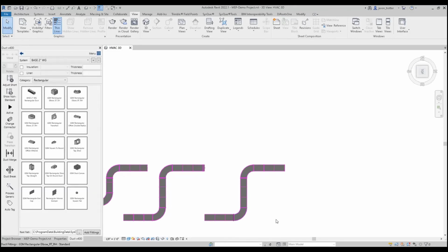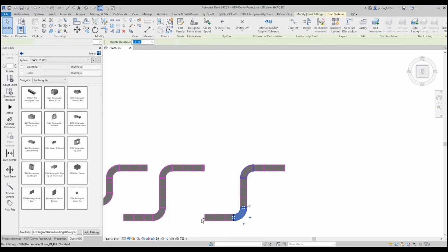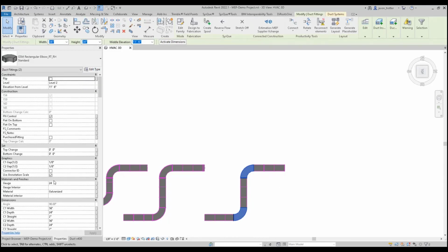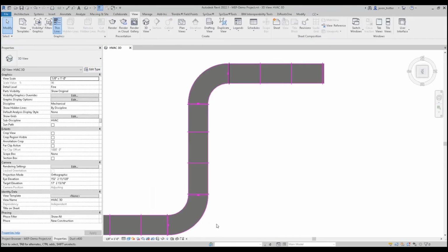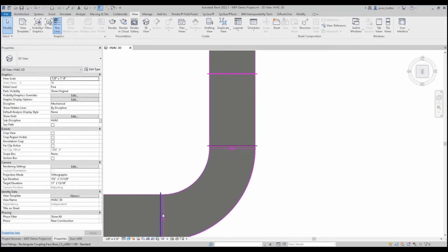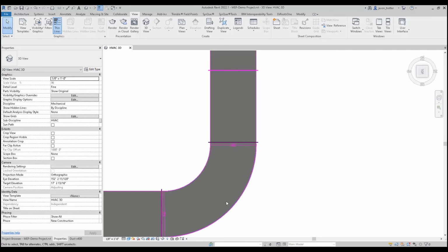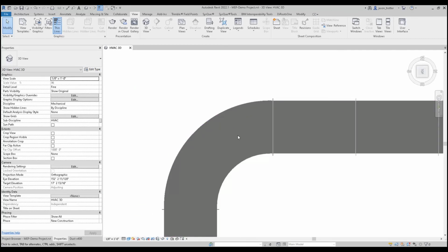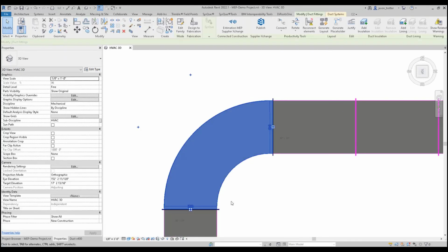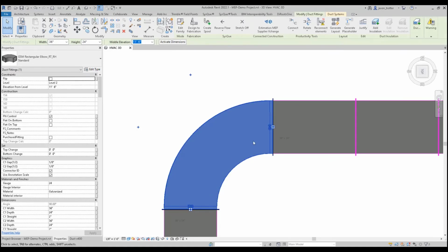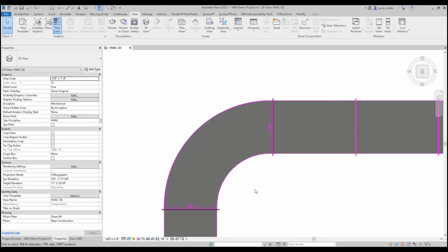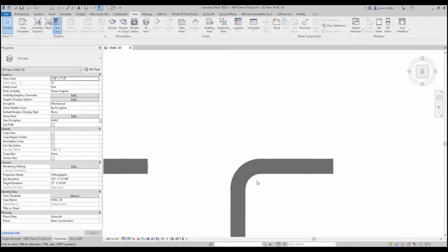The reason being is that when you model elbows in Revit, and this is just an example, there are a couple other scenarios that do the same thing, but if you take a look at the left-hand turn elbow, we modeled from the left to the right, the left-hand turn goes C1 to C2. Now, if I take a look at this right-hand bend, you'll see that it's inverted from the previous run. So this elbow is a C2 to C1. Again, if you know what connector C1 and C2 is, it's still fairly intuitive, but it does break your C1 to C2 flow.